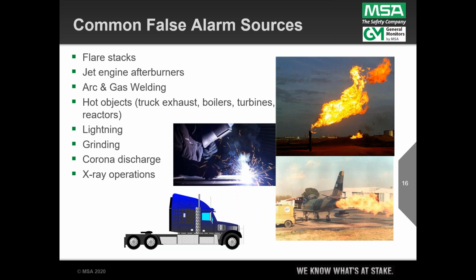And even though FM validates performance of flame detectors to one foot by one foot pan fires of liquid fuels or 32-inch tall gaseous fuels, these flame detectors, regardless of manufacturer, will see a 50-foot fireball. They'll see that a mile away, possibly. I mean, at least certainly 100 yards and beyond, no problem.